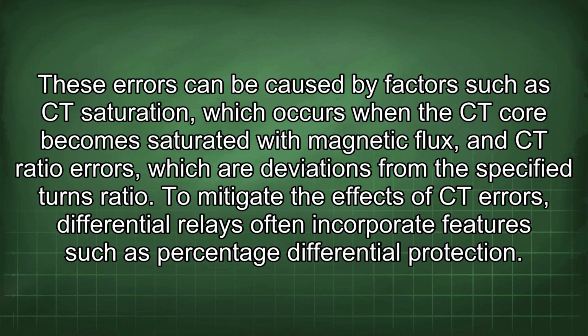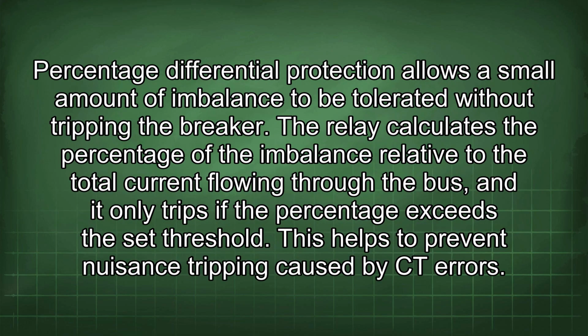To mitigate the effects of CT errors, differential relays often incorporate features such as percentage differential protection. Percentage differential protection allows a small amount of imbalance to be tolerated without tripping the breaker. The relay calculates the percentage of the imbalance relative to the total current flowing through the bus, and it only trips if the percentage exceeds the set threshold. This helps to prevent nuisance tripping caused by CT errors.